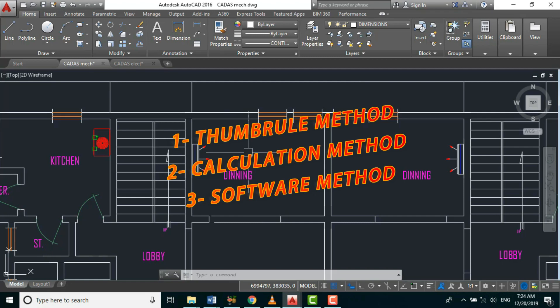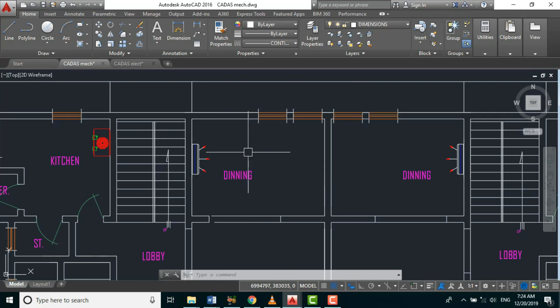We also have 0.08 for medium load areas such as bedrooms, offices, and living rooms. And we have 0.09 — we multiply our space area by 0.09 to determine the tonnage requirement for high load areas such as supermarkets, auditoriums, etc.